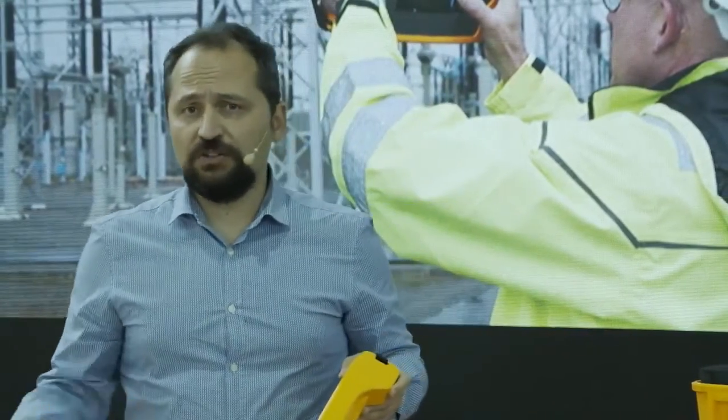So that's as simple as that. Once I have it, I will just push this green button, wait 1 minute, and then I have the actual severity here. It's telling me that it's 3/10 severity, so it's not that important. And the distance is almost 1 meter far away in this case. It's pretty close. Then I can document it, and once I have documented it, I can save it, and that's ready. I have it in my internal memory, ready for me to go to my laptop and generate the report with the cost estimation. Okay?